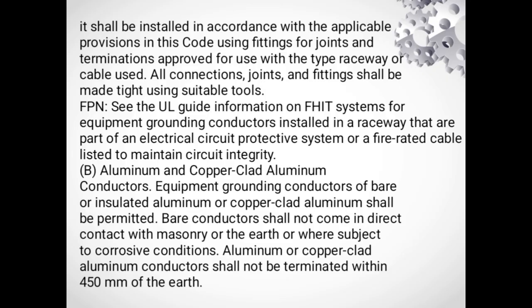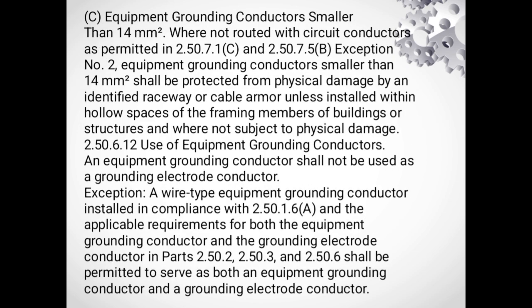Bare conductor shall not come in direct contact with masonry or the earth or where subject to corrosive conditions. Aluminum or copper clad aluminum conductor shall not be terminated within 450 mm of the earth. C. Equipment grounding conductors smaller than 14 mm² where not routed with circuit conductor as permitted in 2.50.7.1c and 2.50.7.5b, Exception number 2. Equipment grounding conductors smaller than 14 mm² shall be protected from physical damage by an identified raceway or cable armor unless installed within hollow spaces of the framing members of buildings or structures and where not subject to physical damage.